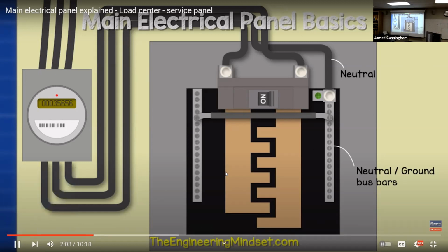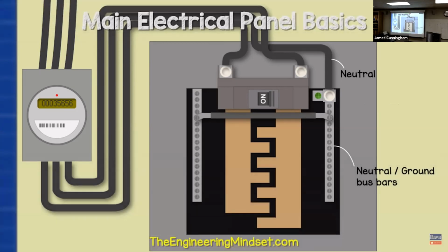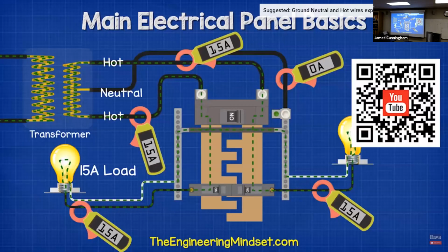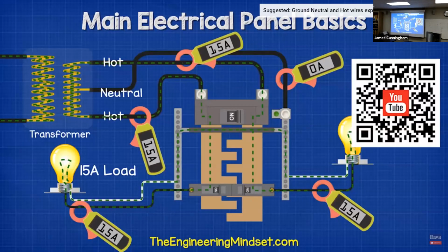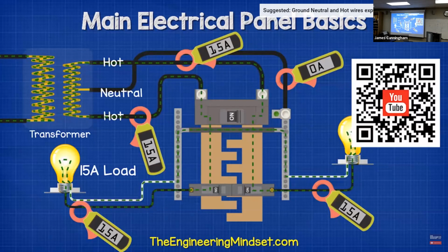We have the neutral wire connected to the lug on the top of the neutral ground bar. Notice the green screw. This is bonding the neutral bar to the metal casing of the service panel. The purpose of the neutral bar is to return the electricity back to the transformer. It does actually get a little bit more advanced than that, but we're going to look at that in a more advanced, complex video. This is just covering the basics.